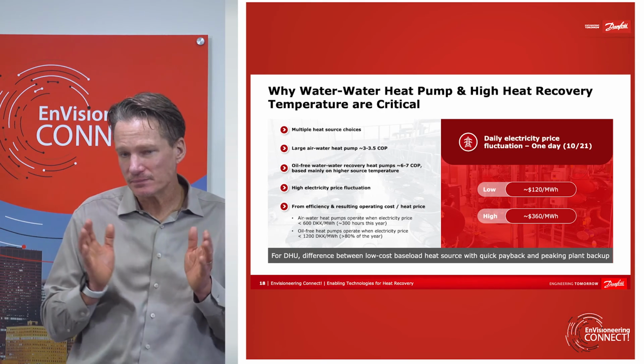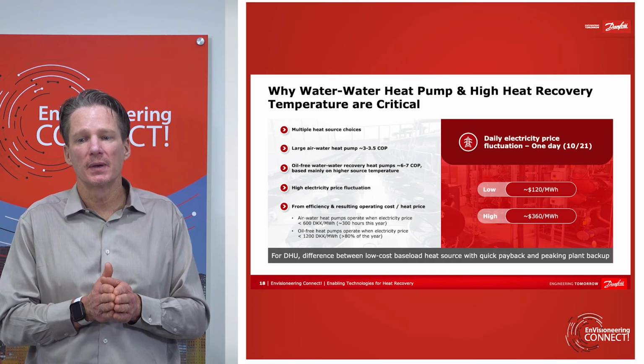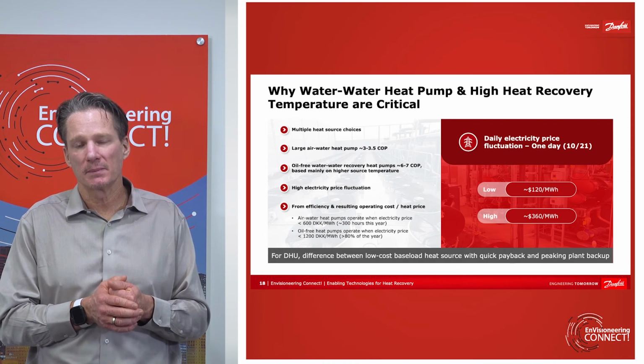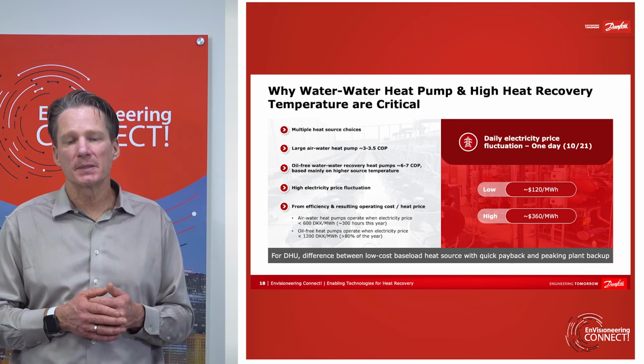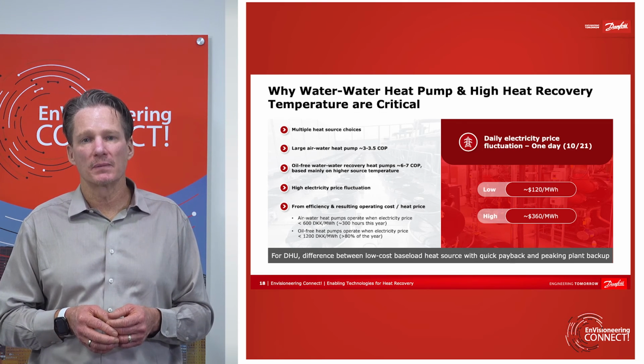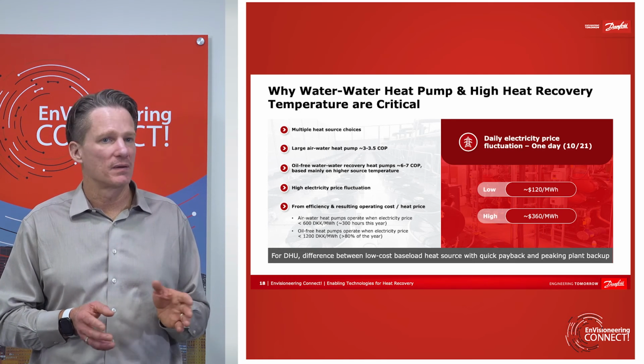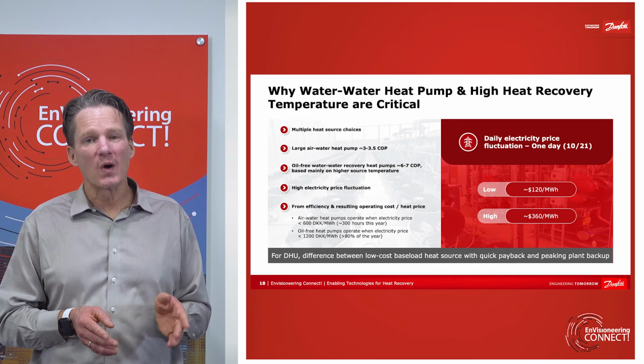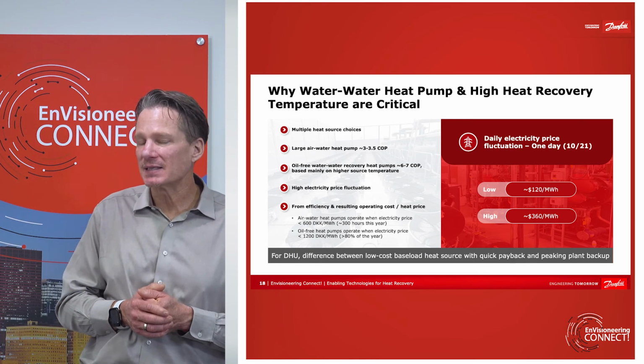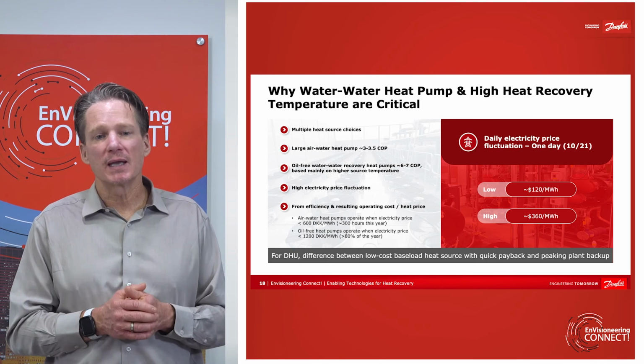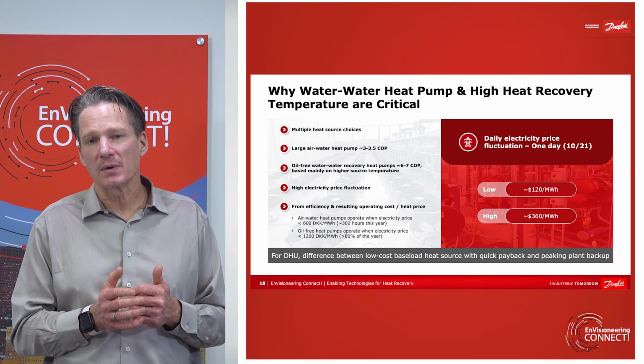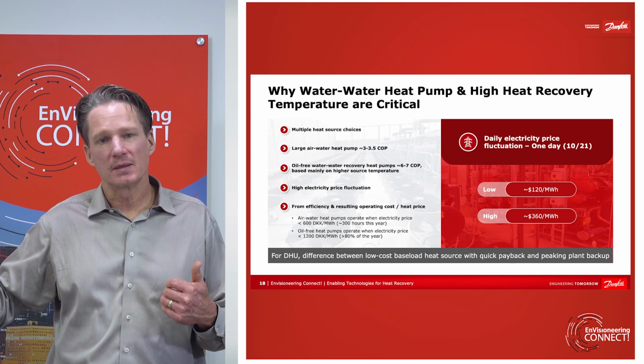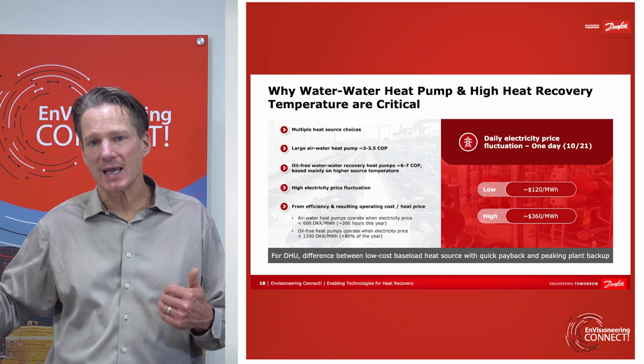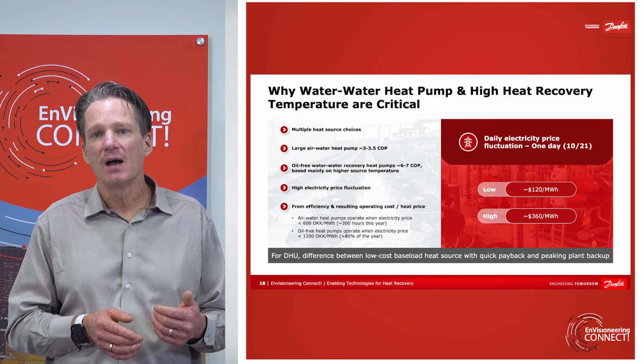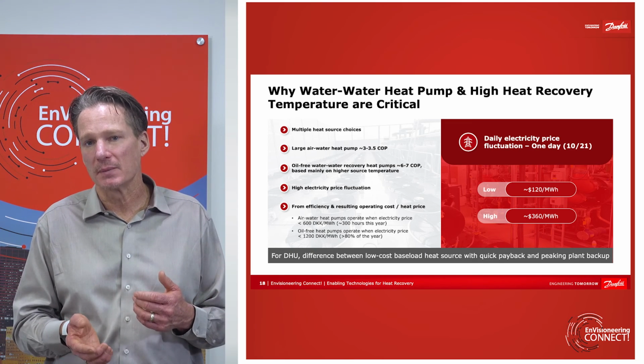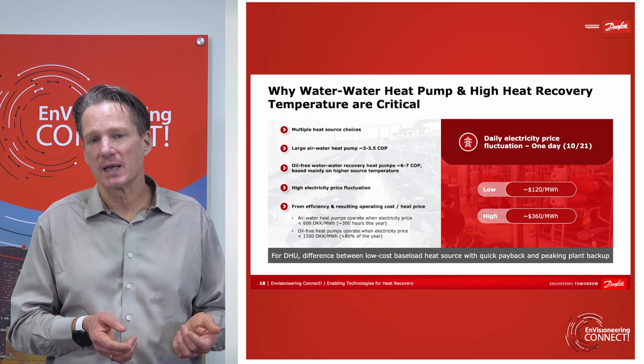And this is showing why that's critical. Why is it really critical to make sure that you implement the most efficient and highest availability water-to-water heat pump system? This is showing a snapshot of the energy prices that we've seen and the fluctuations of them in Denmark over the last 6 months. And actually, on the left-hand side of the chart, it shows the variation in just one day in the energy cost. That's because of that same integration of renewables factor. So Denmark today is about 50% renewables in the power grid. Today in the US, we're at about 20%. As we grow up to the percentage that Denmark is at today, we're going to see these same very high daily price fluctuations of electricity cost because of the periodic unavailability of the sun and wind to supply the grid.